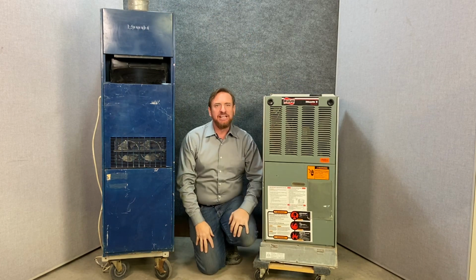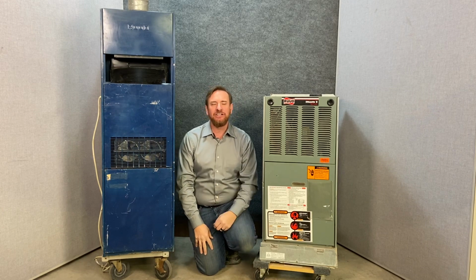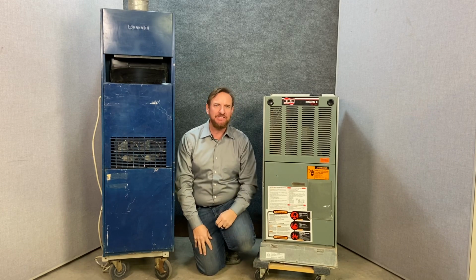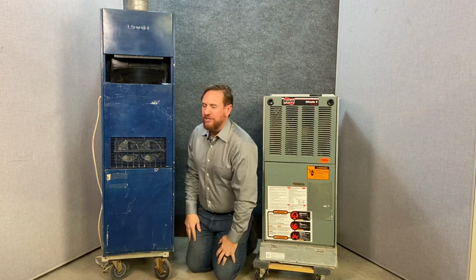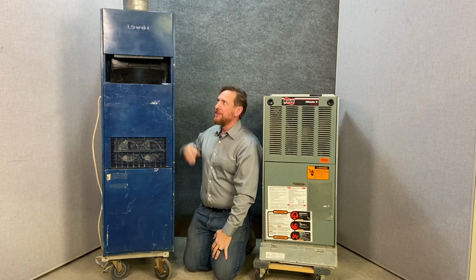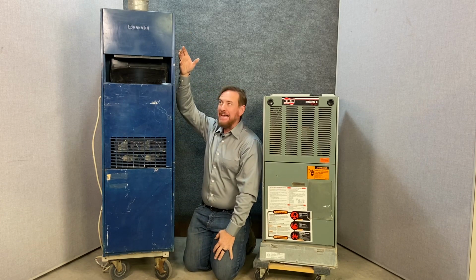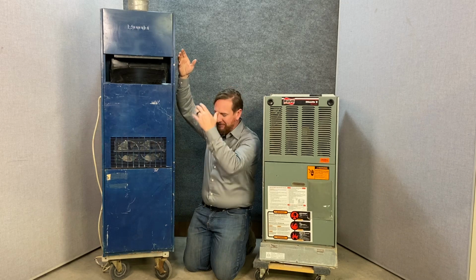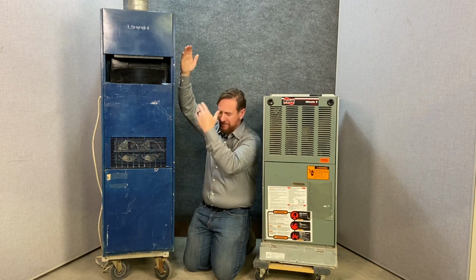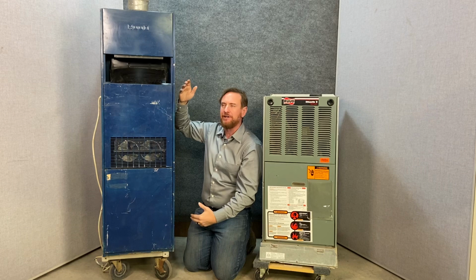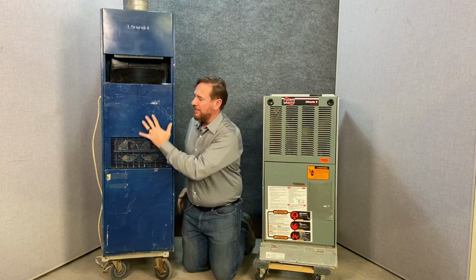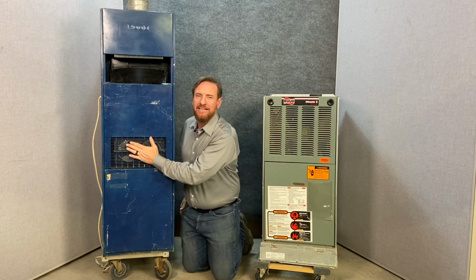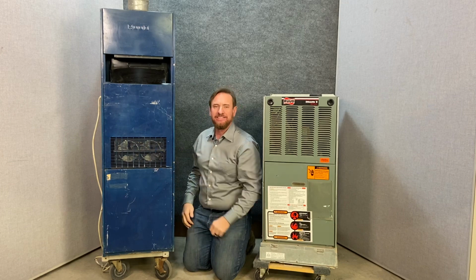If this was installed in a closet, the air in that closet has to be separate from the air of the house. So the closet would have what you call upper and lower combustion air. There would be a pipe coming from the attic into the closet, say about halfway, and another one coming within so many inches of the top, and another one coming within so many inches of the bottom. That air coming into the closet is what's going to be burnt right here in this furnace. It's very important that it stays separate.